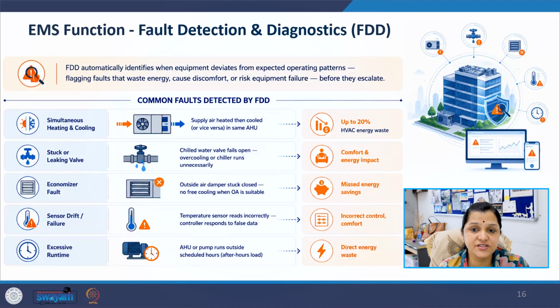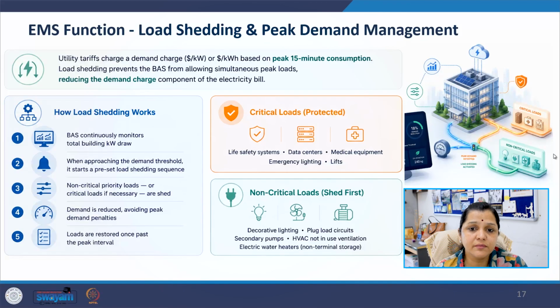This wastes significant energy unnecessarily. Another frequent issue is a leaking or stuck valve that causes excessive cooling or heating. Economizer faults may prevent the system from using favorable outdoor air conditions for free cooling. Sensor drift is another important problem because inaccurate sensors lead to incorrect control responses. Excessive runtime outside scheduled operating hours also creates direct energy waste. So fault detection and diagnosis systems detect these types of conditions automatically before they escalate into larger operational or equipment failure. Next is load shedding and peak demand management.